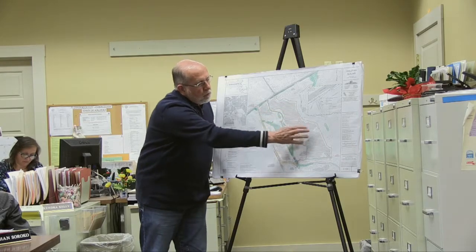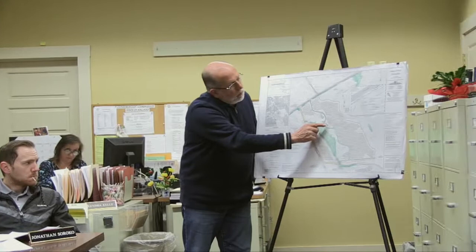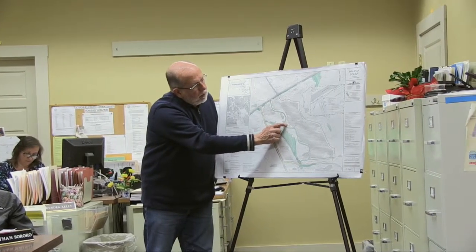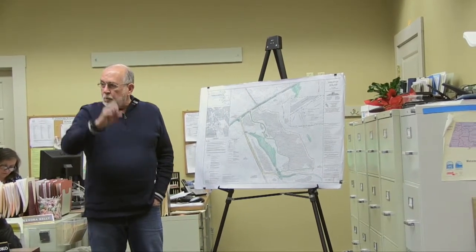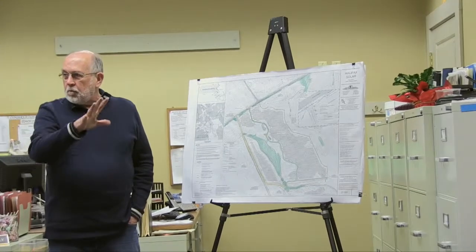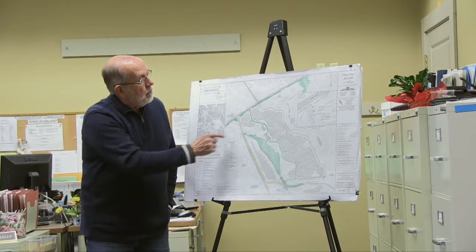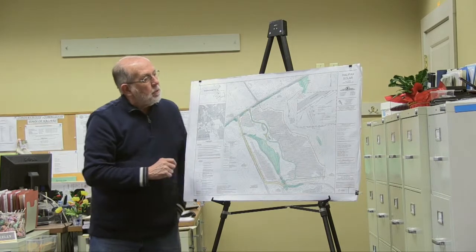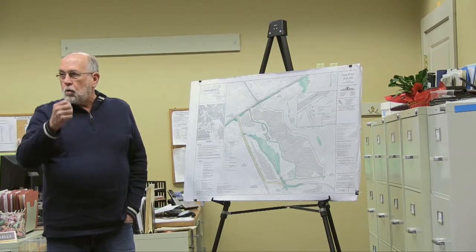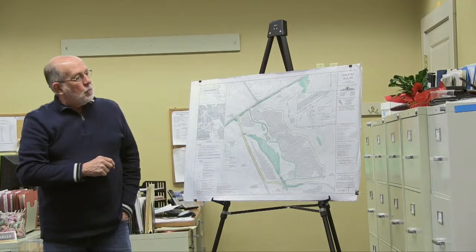These are the solar strings, the solar array. It's a 5 megawatt array. They're basically brought to control inverters, a transformer pad, and a large bank of batteries, which basically helps the grid a lot. When a cloud comes over, it's not suddenly dimming and going strong, pulsing. It also provides output when there is no sun. Everything's run underground, right to the street, where there are 3 poles for the recloser and metering, and then it just ties into the existing cables that are on the ground.